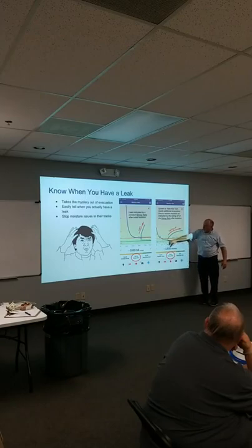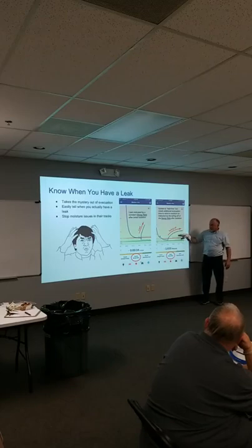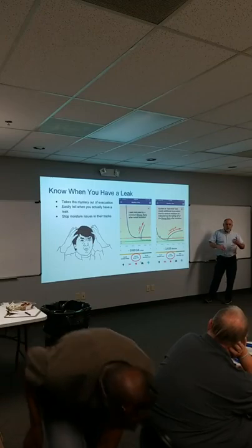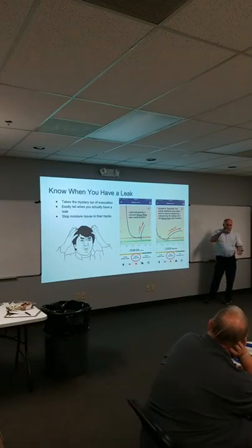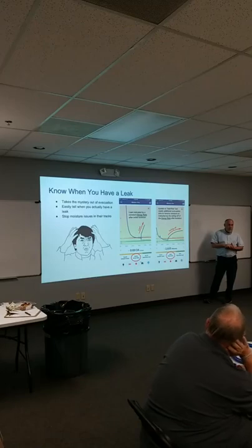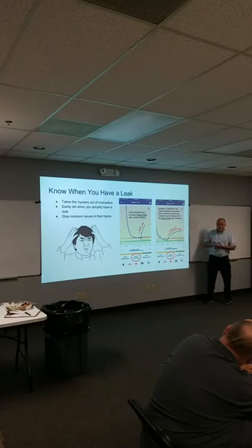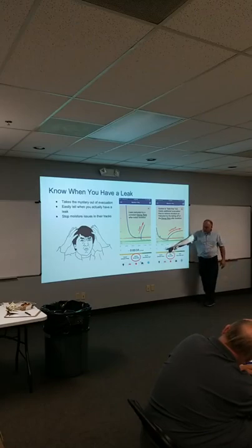When you isolate and you have moisture, it tails off like this. And this tailing off is just a buildup of vapor pressure. Notice where that's tailing off at around 2,600 microns. Water vapor is going to be somewhere around 1,500 to 2,000 microns, depending on the atmosphere or the temperature, right? The colder the temperature is, the lower this is going to be. The higher the temperature is, the higher this will be, because warmer air can hold more moisture.